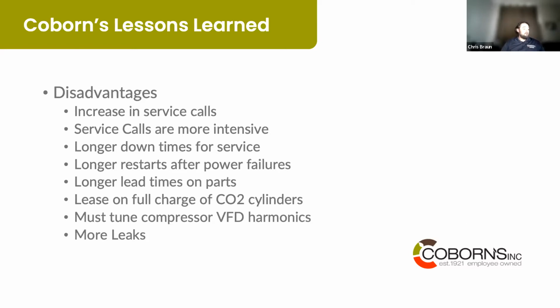There also is the lease, like Doug talked about, on the CO2 cylinders for a full store recharge. We do keep a full store charge on site at all 3 sites. Not only is there a CO2 cylinder availability problem, but you're also paying a monthly lease on that, which after a year on 3 stores does add up. One thing that we learned is that you do have to tune your compressor VFD harmonics. With the compressor manufacturer and the drive we use, there seems to be a certain harmonic that does cause excessive vibration. Once you tune those, that does go away.